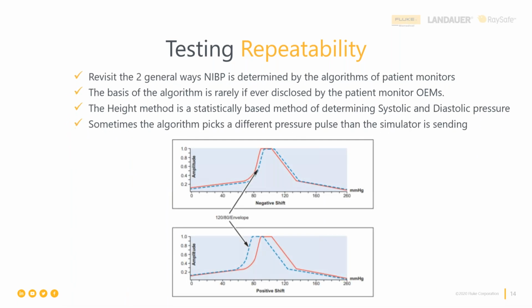So sometimes if the pressure is picked a little incorrectly, it would be nice to be able to maybe shift that. And remember, we can do that because we're not cheating here. This is not about accuracy. But if we can help the patient monitor pick the right pressure in the cuff, we're much more likely to get a measurement that looks a lot closer to the signals that we're sending into the patient monitor. And we would like for that to happen because while we're looking for repeatability, we're also looking for stability of this measurement system. So it's a lot more that you ought to be thinking about when you're doing these tests in your mind than just hooking up the cuff, hooking up your test instrument, running the dynamic sim, and writing down whatever you write down.